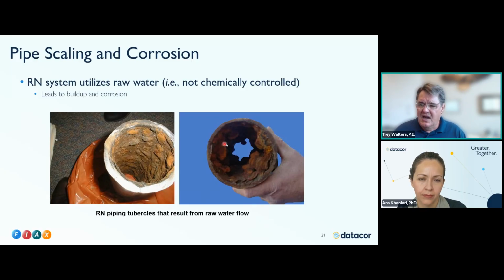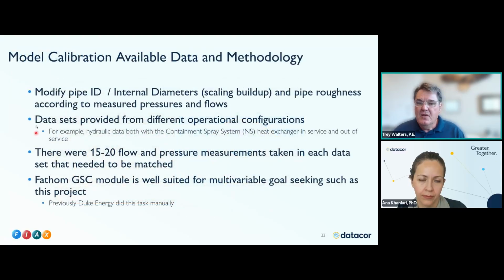Okay. So you can see obviously there was fouling, which would affect the diameter of flow, which increased the velocity. And I don't know what you do with the roughness on here, but we were able to do some calibration to try to estimate what these were by matching against data. Okay. So there's modification of the internal diameter of the pipes because of scaling and modification of the roughness.